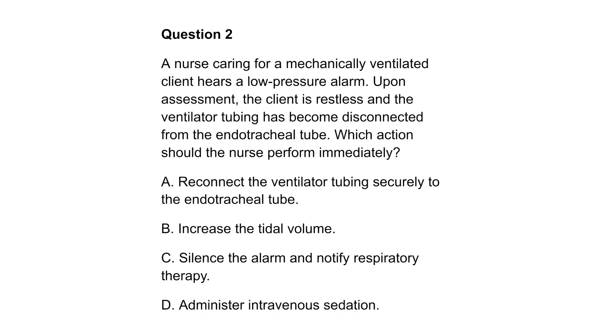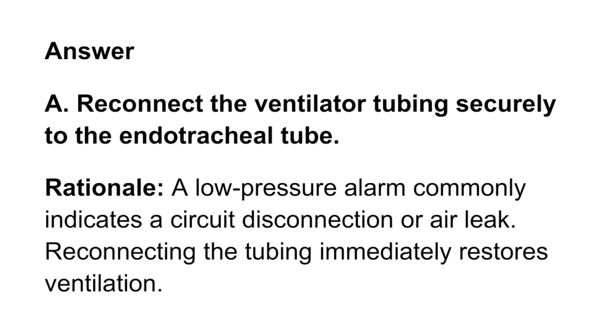Answer. A. Reconnect the ventilator tubing securely to the endotracheal tube. Rationale. A low-pressure alarm commonly indicates a circuit disconnection or air leak. Reconnecting the tubing immediately restores ventilation.